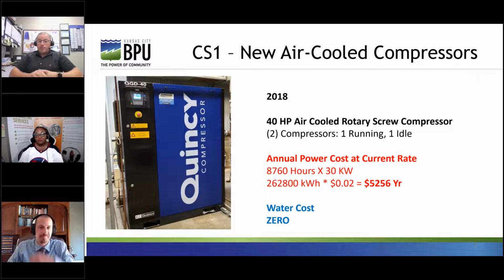There were no water calculations for these, obviously, because there was no water going through them, and they're still in the same operating mode, 1 in service and 1 in standby. These newer compressors consume around $5,200 in electricity annually, and that's about $1,226 less than their predecessors, and they also require fewer PMs per year. So that's case study 1 out of the way.